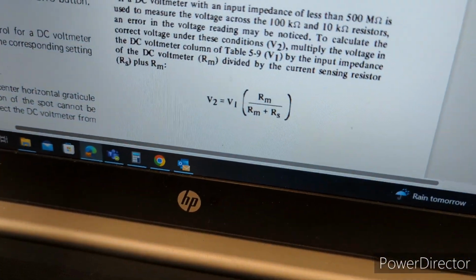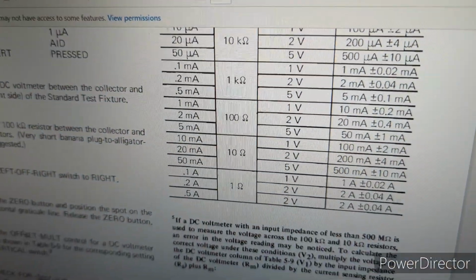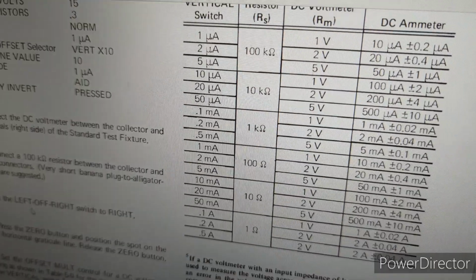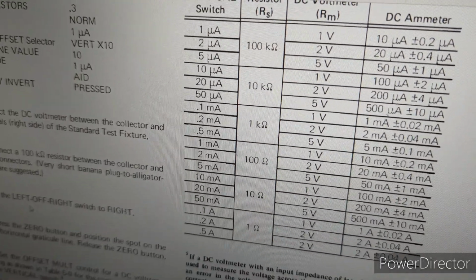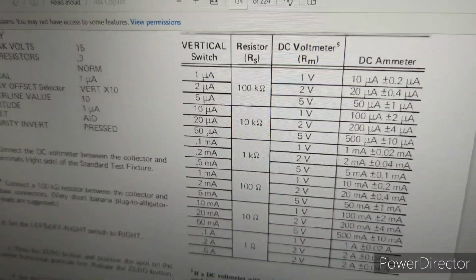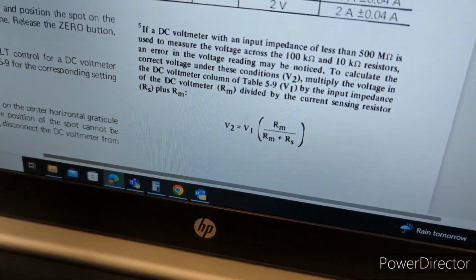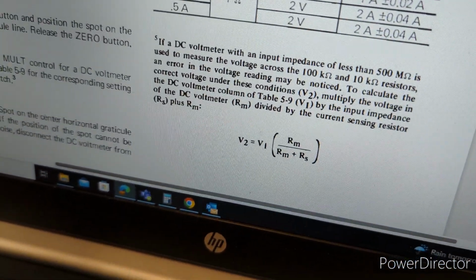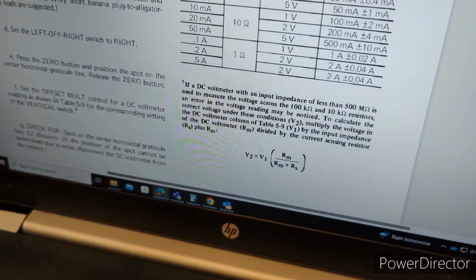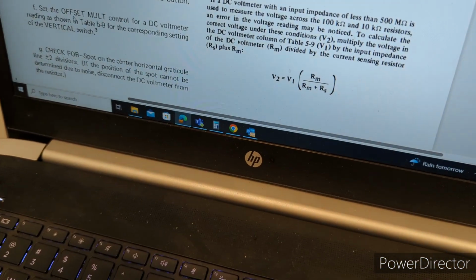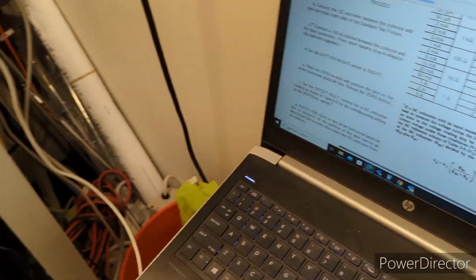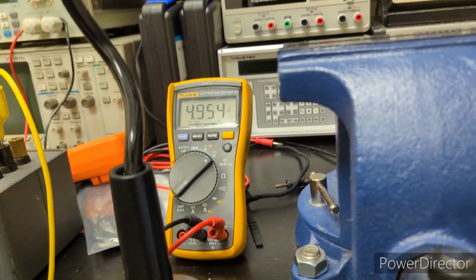Okay, so when I do that calculation that is in the manual, for example, for the 5 microamp setting of the switch using a 100k ohm resistor, the DC voltmeter should be reading 5. So for that setting, V1 is equal to 5, and then you multiply that by Rm, which is the input impedance of that meter. So I put 10 mega ohms and divided that by 10 mega ohms plus 100 kilo ohms, and I got 4.950. And now I've centered it, and my meter's reading 4.954.